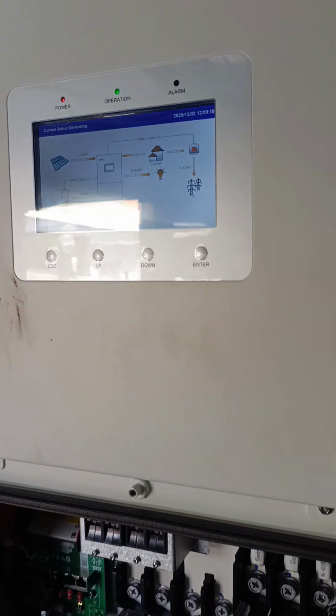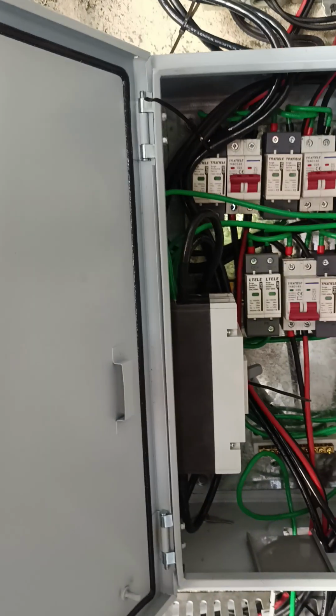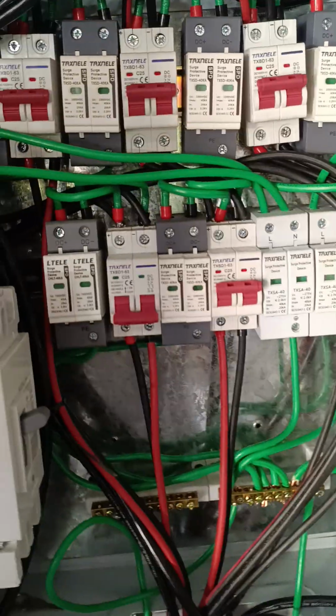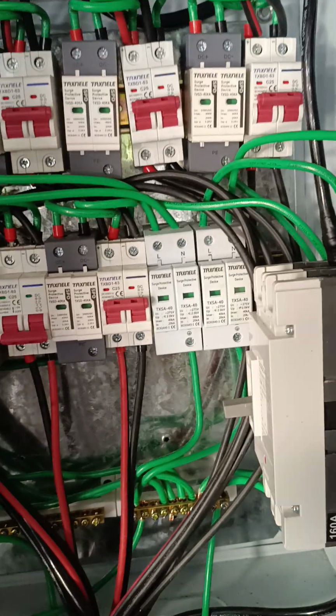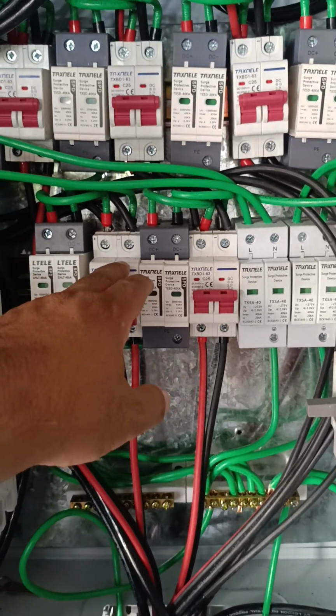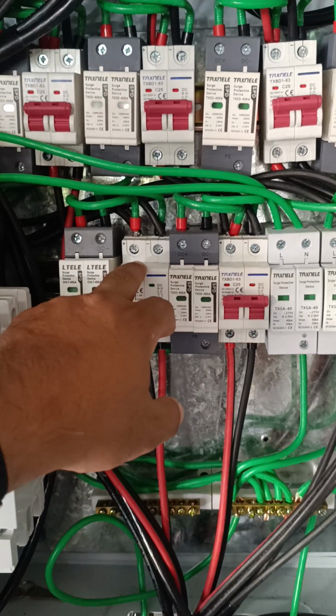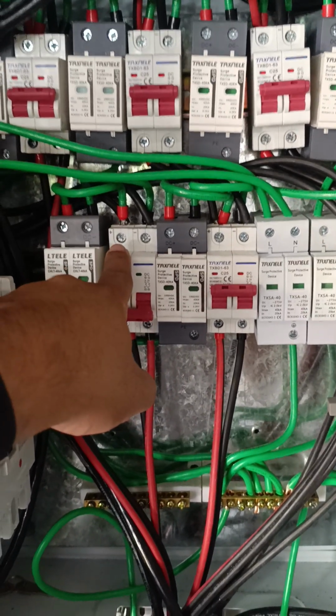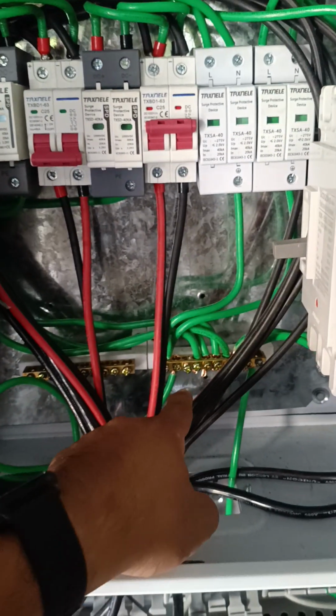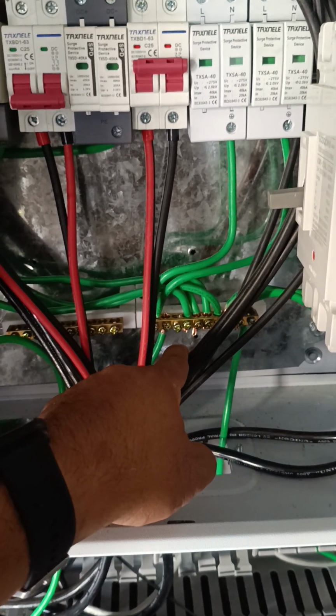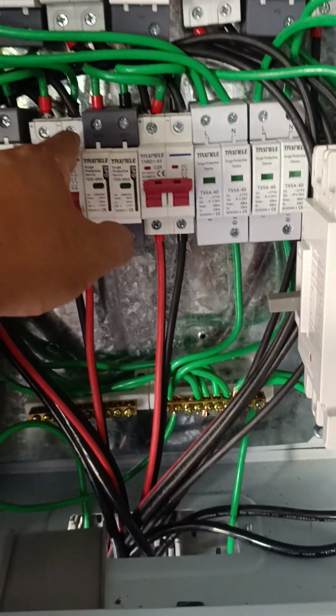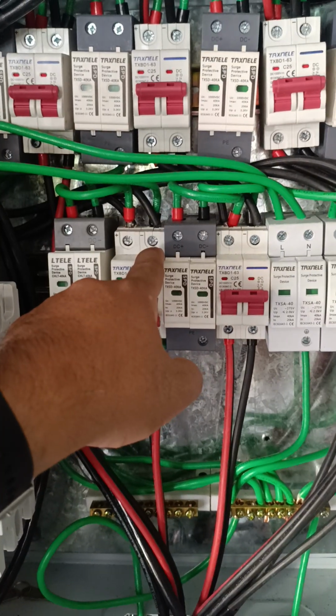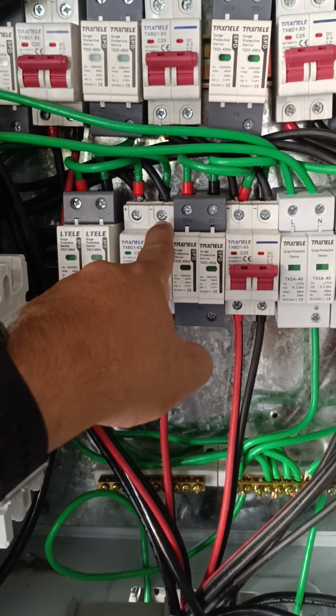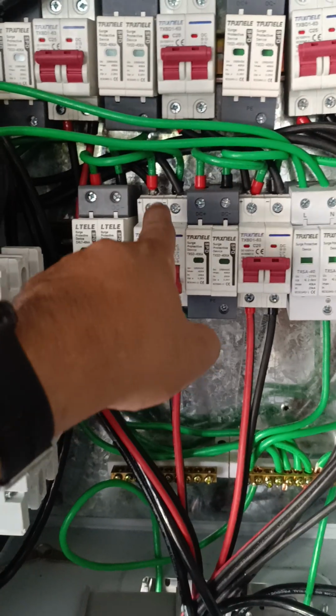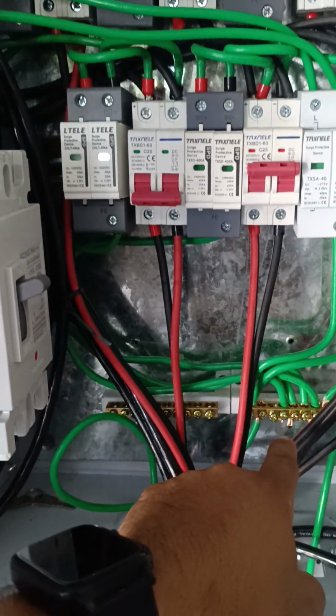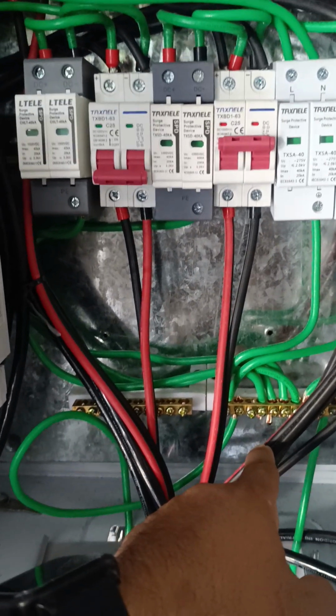error 1033. So what we did was we isolated again, turned off again the system, then we tested this PV string with a multimeter. Okay, we put the positive probe here and then the negative probe onto the grounding, to the earthing. Also tested the negative side of the string using the connectivity of the multimeter.